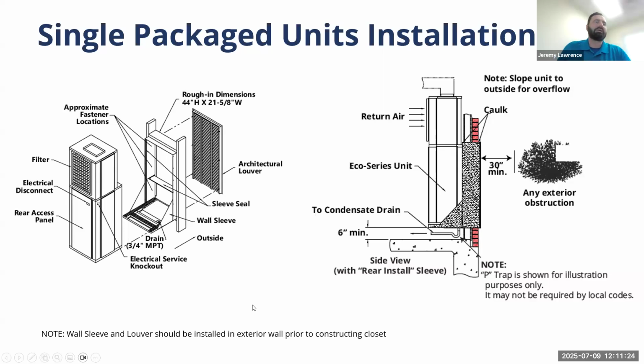A big feature of the way that First Company does these PTACs is that these architectural louvers or grills are installed from the inside of the building. So regardless of the height or the configuration of the building, these can be installed from inside, and no one needs to be hanging off the side of the roof or on a boom lift or cherry picker. So the grill gets installed from inside and screwed to the sleeve, and then the unit sits onto the sleeve. The sleeve is weight bearing and becomes part of the drainage system as well.